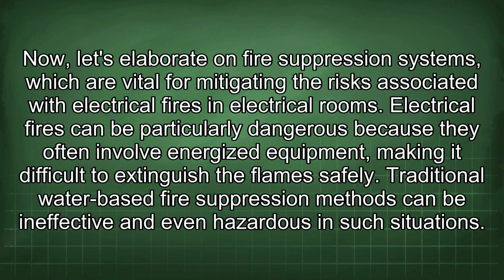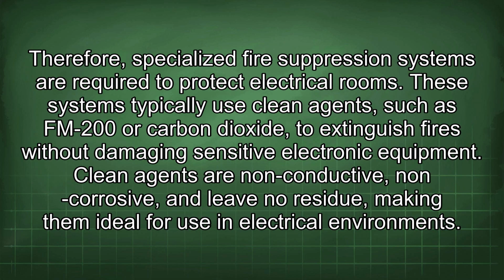Now, let's elaborate on fire suppression systems, which are vital for mitigating the risks associated with electrical fires in electrical rooms. Electrical fires can be particularly dangerous because they often involve energized equipment, making it difficult to extinguish the flames safely. Traditional water-based fire suppression methods can be ineffective and even hazardous in such situations. Therefore, specialized fire suppression systems are required to protect electrical rooms. These systems typically use clean agents, such as FM-200 or carbon dioxide, to extinguish fires without damaging sensitive electronic equipment. Clean agents are non-conductive, non-corrosive, and leave no residue, making them ideal for use in electrical environments.